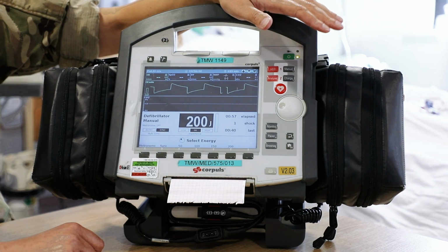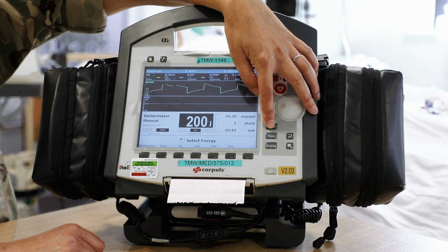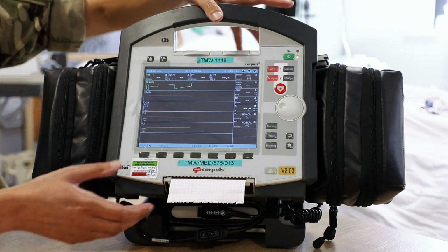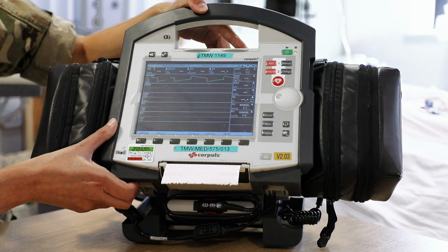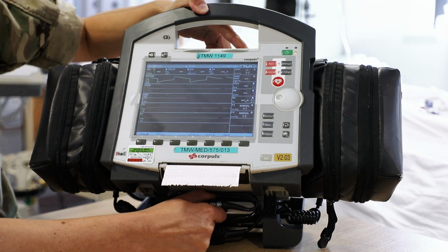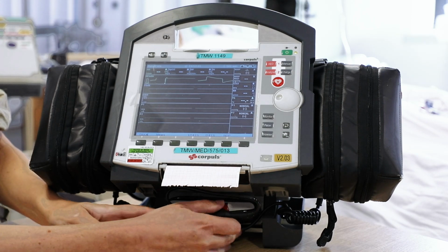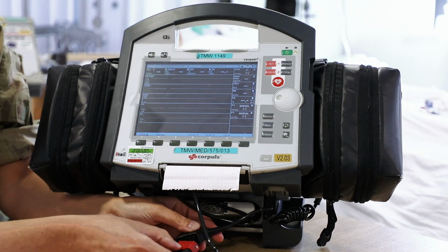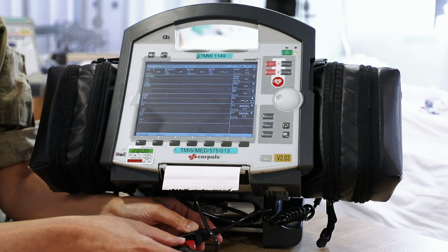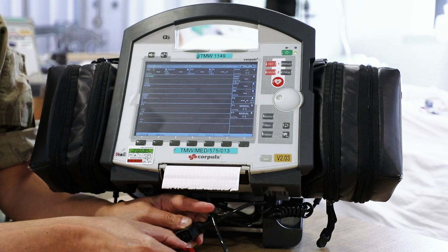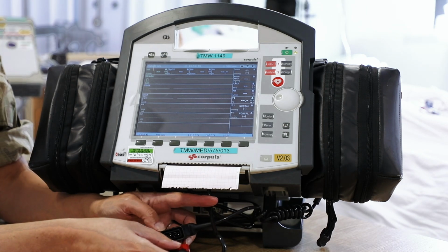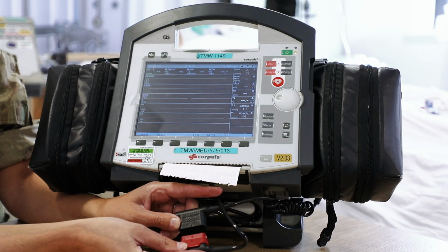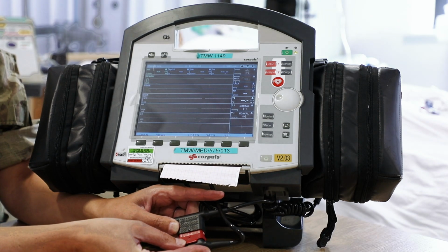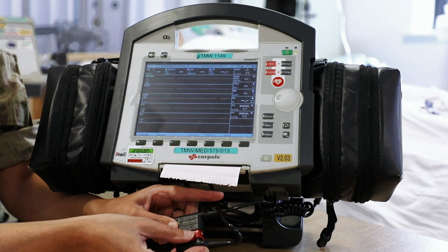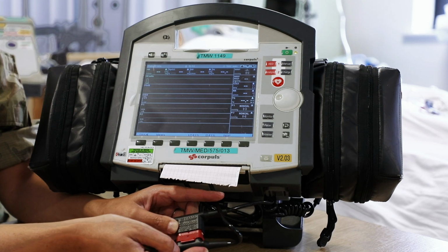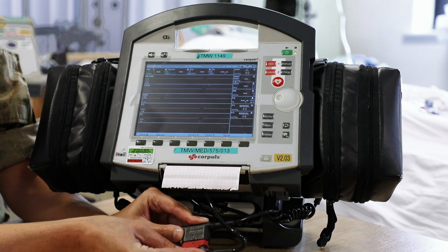To move into test number 3, we need to fully disarm the defib. So we'll do that by pressing the monitor button, and we're going to return to our red master cable, where we are going to connect it to our paddles. Now obviously if you don't have paddles connected routinely, you don't need to proceed onto this test, but I would recommend that if you're ever likely to use the paddles, you should remove them periodically and perform this test just to confirm that they work. So with the paddles, we're going to connect them up at the base, and you just connect the red master cable to our paddles. And if you're trying to do this in the dark, one way to notice is that there's a raised button on your cables which indicate how it's going to fit. So just clip those two together.